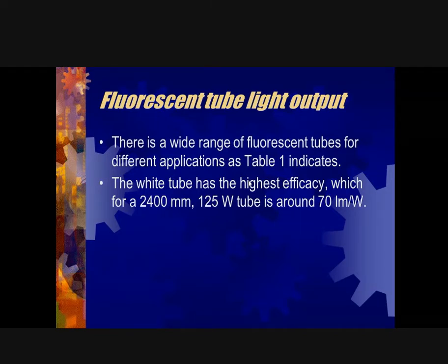But when you have a facility with many lamps, converting all of them to LED will definitely affect the bill. We have to have a lot of them to see any difference. If we're talking about one or two lamps, you will not see much difference because of the high efficacy of fluorescent tubes. So for a typical 125 watt tube, we will get about 70 lumens per watt.